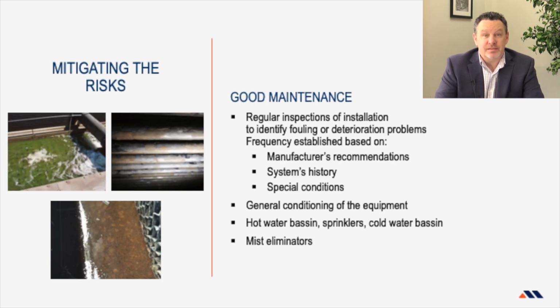Some of the other basic things that need to be done for a cooling system that help is just basic housekeeping. Make sure things are clean. If you see accumulation at the bottom of the cooling tower sump, clean it up. If you see that the mist eliminators are broken or they're fouled with a collection of garbage bags carried in the air or something, make sure you remove them. Some basic housekeeping is important.